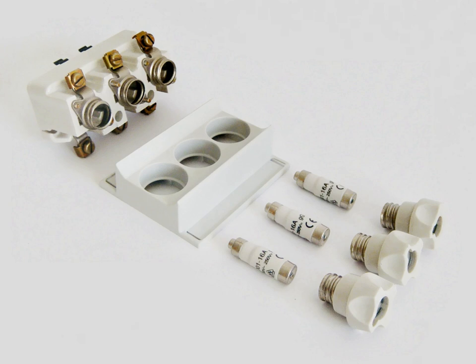Any fuses built to the IEC 60269 standard and carrying the same application category, for example, GG or AM, will have similar electrical characteristics, time current characteristics, and power dissipation as any other, even if the fuses are made in the packages standardized to the earlier national standards. Fuses of the same application category can be substituted for each other provided the voltage rating of the circuit does not exceed the fuse rating.